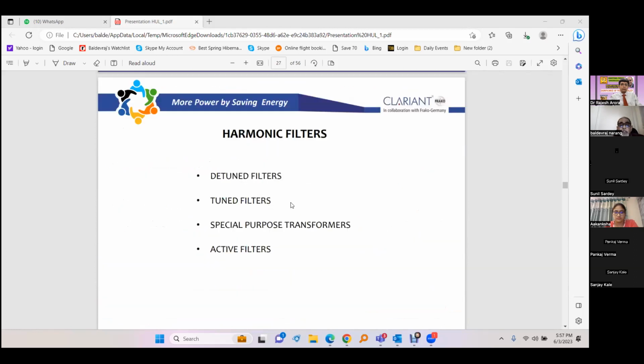So we have discussed the passive systems where we can remove harmonics, because mostly we have 5th and 7th harmonics. Third harmonics are in loads which are predominantly single phase. Otherwise, it is 5th and 7th harmonic. So for the third harmonic, we use a 14% reactor. We tune the reactor close to the third harmonic frequency. And for 5th and 7th, we tune it close to 250 hertz. So that is how filtration is done.